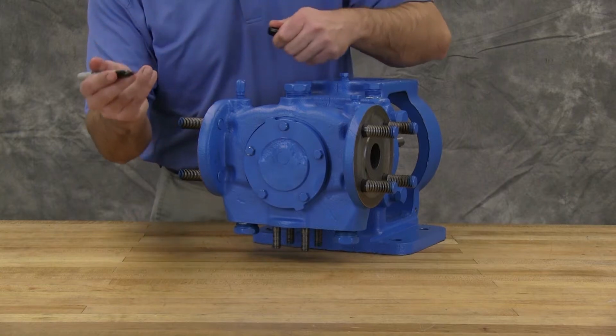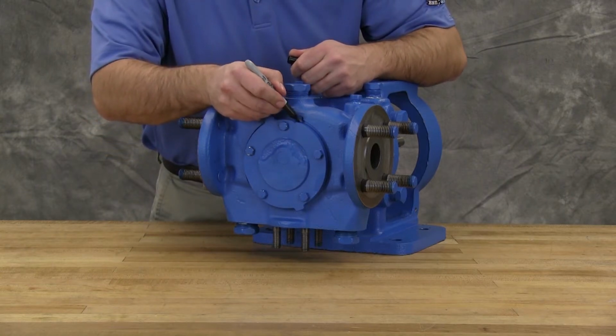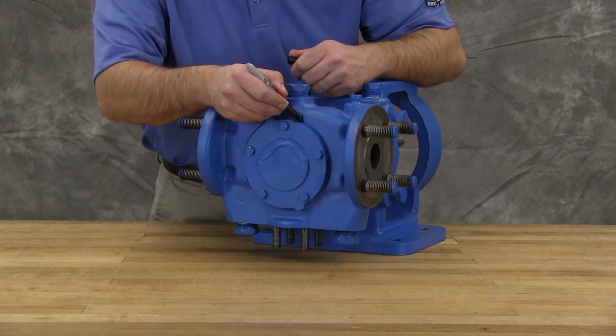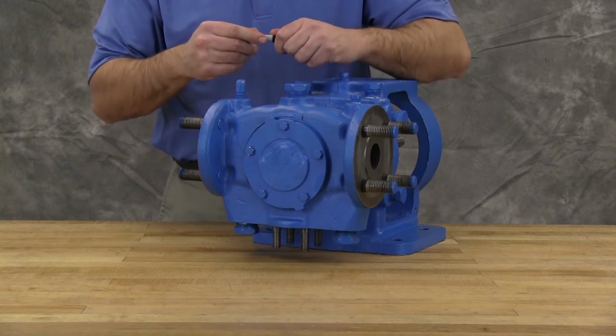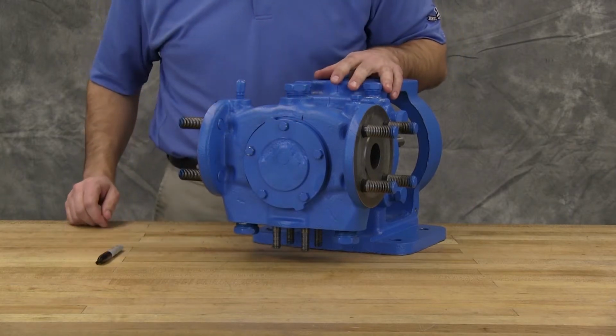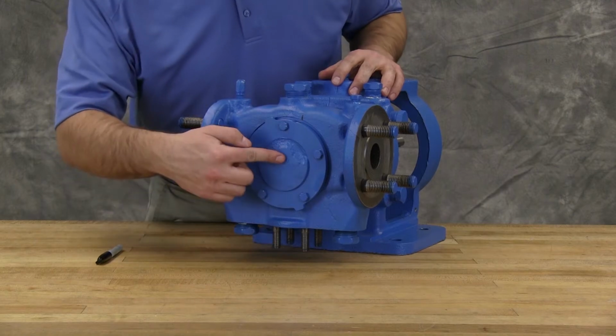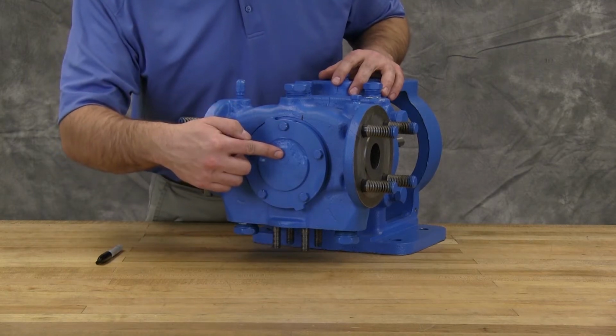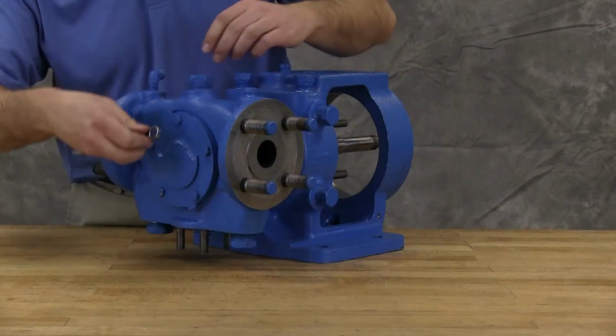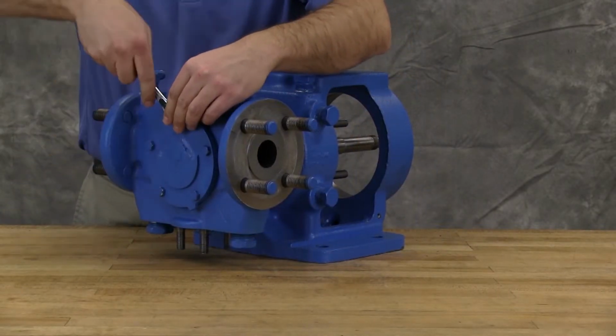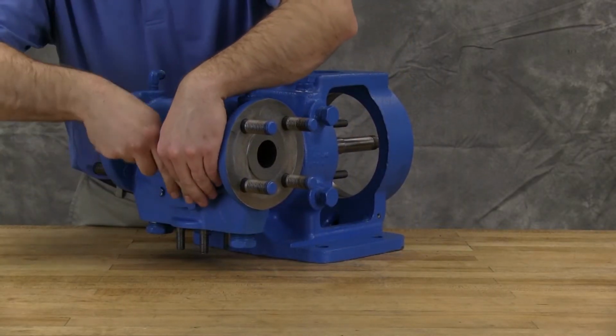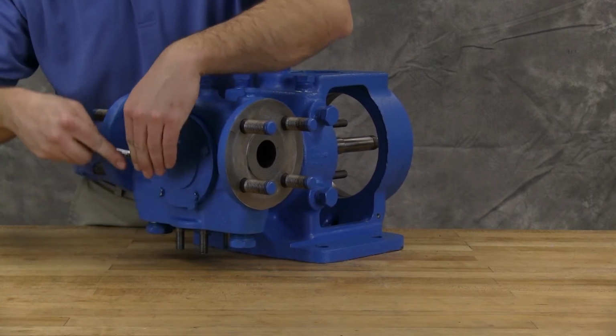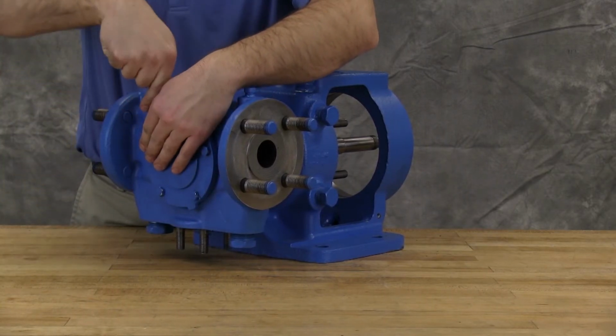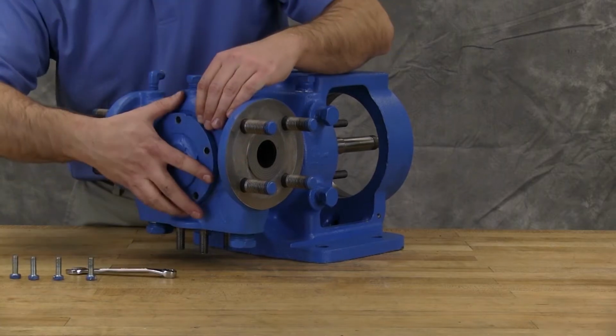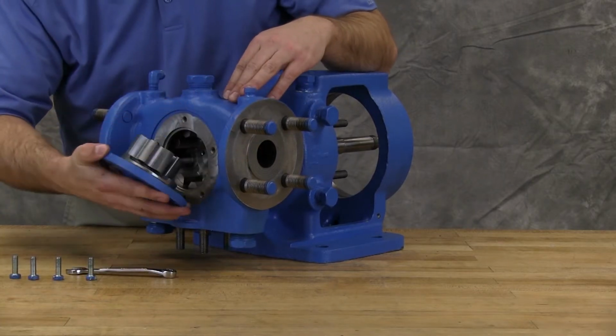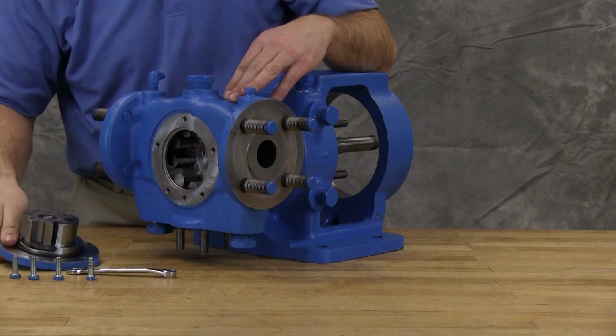Mark the head and casing before disassembly to ensure proper reassembly. The idler pin, which is offset in the pump head, must be positioned toward and equal distance between port connections to allow for proper flow of liquid through the pump. Remove the head cap screws or nuts. On larger pumps, jack screws should be used to back the head away from the casing. Remove the head by tilting it backward to prevent the idler from falling off the pin.